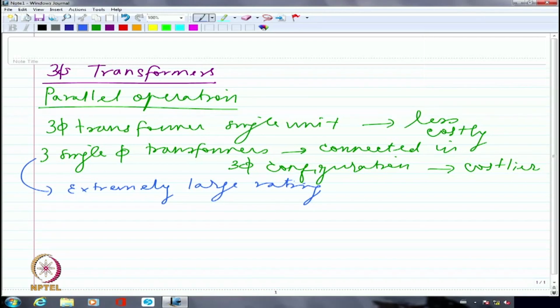So when I look at the single phase transformer being connected as a three-phase transformer unit, the major advantage, as I told you, one is flexibility. Second is the portability is better, because if I have three-phase units together, it will be extremely bulky. Imagine a 400 MVA transformer. Each single phase is going to have about 150 MVA rating. Obviously, transporting a 150 MVA transformer will be simpler as compared to transporting one single 400 MVA transformer. So, definitely, we are essentially retaining.